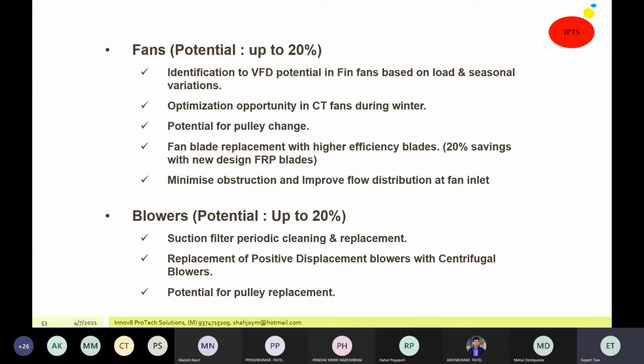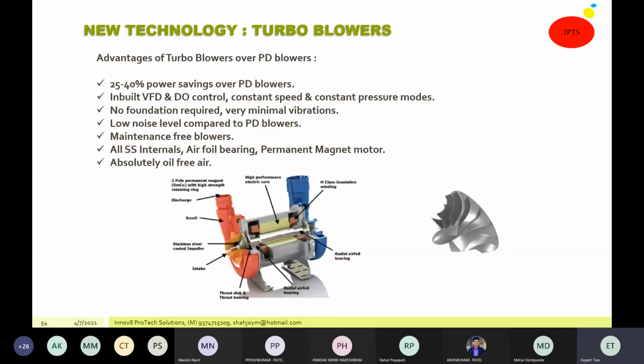And suppose if you have a pulley, perhaps I am not in favor of pulley because pulley is always a low efficiency drive. So always look for some other means of transmission of the energy, preferably direct mounted. New technology which is available is the turbo blower. It offers advantages over the PD blower. It offers almost 25 to 40% higher efficiency, and that is why people are now replacing their blower with the turbo blower for improving the efficiency and reducing the energy consumption.